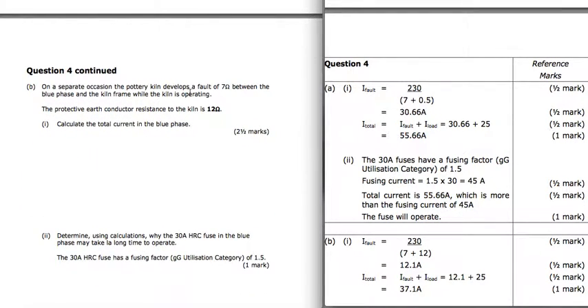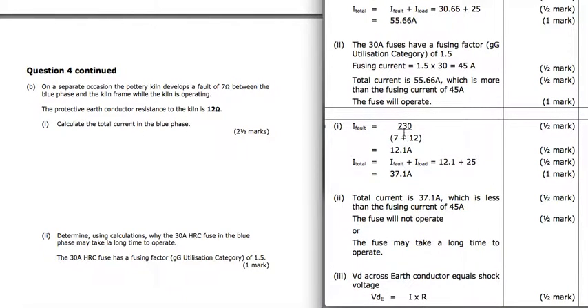Now it's the same kiln, same fault here, but we've got an earthing conductor now of 12 ohms. So that should ring alarm bells in your head. 12 is way too high. The total current, that fault current, is going to be much lower. So let's have a look at that. We've got 230 divided by 7, which is our fault, plus 12, which is our conductor resistance. And that only gives a current of 12.1. And if we add that to the 25 of the normal red supply current, we get 37.1.